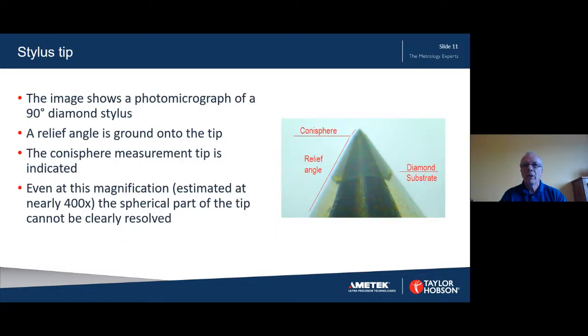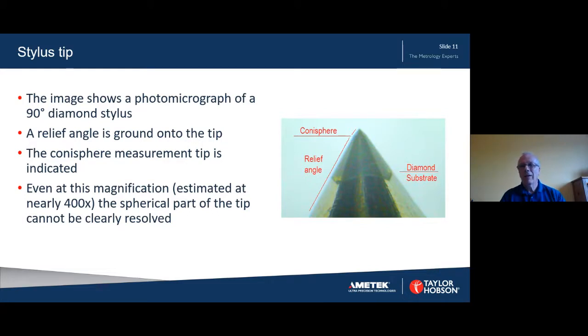This image shows a 90 degree conisphere tip. The diamond is brazed or bonded into a metallic substrate and ground to a cone angle. The relief angle is slightly smaller than the desired angle — in this case, slightly smaller than 90 degrees. The very last part of the tip is then ground and polished to achieve the required radius and included angle. Because of its small size, it's extremely difficult to image the tip itself even with a scanning electron microscope, because we're trying to take a profile of a 3D object which is a cone.